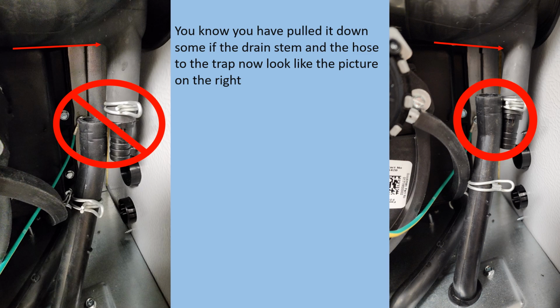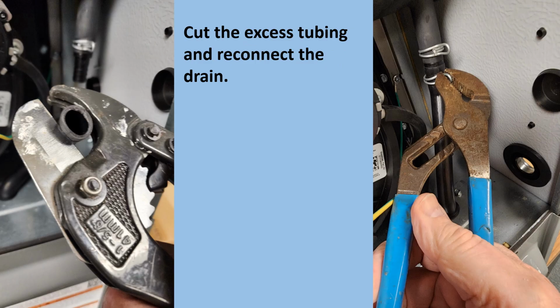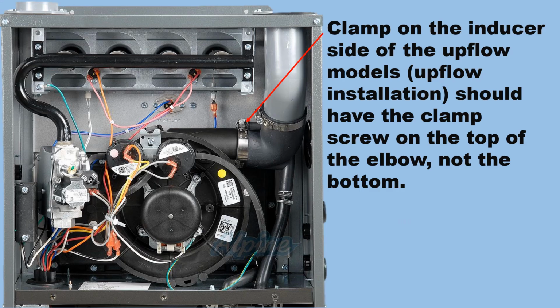You know you have pulled it down some if the drain stem and the hose to the trap now look like the picture on the right. You see there that you have that little bit of extra on there. Cut the excess tubing, and reconnect the drain. The clamp on the inducer side of the upflow models, upflow installation, should have the clamp screw on top of the elbow, not the bottom.